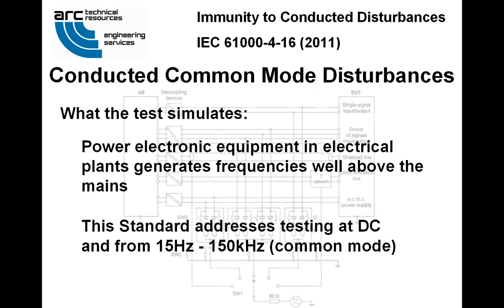Immunity to conducted disturbances, 61000-4-16. Conducted common mode disturbance testing simulates power electronic equipment in electrical plants, which generates frequencies well above the mains. The standard addresses testing at DC, and then separately from 15 hertz to 150 kilohertz in common mode only. Substation equipment usually tests at level 4, that's a 30-volt EMF level. An audio amplifier is usually used for the first 3 segments up to about 15 kilohertz, and an RF amplifier is appropriate for testing from 15 kilohertz to as high as a megahertz, using 10% step sizes and a 10-second dwell time, while the acceptance of the EUT is assessed. And once again, you may also need to investigate other frequencies between those 10% step sizes if they're related to the operational frequencies inside the product.